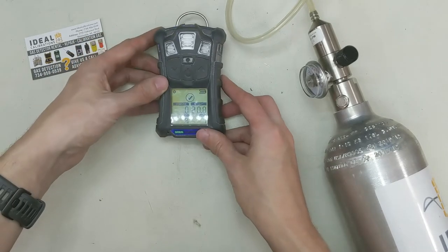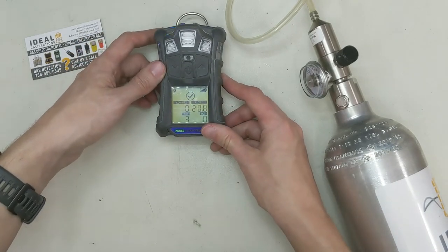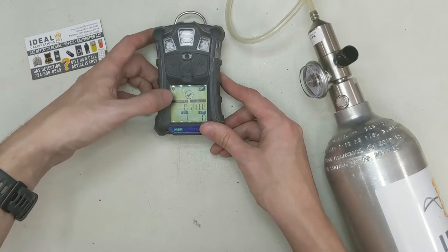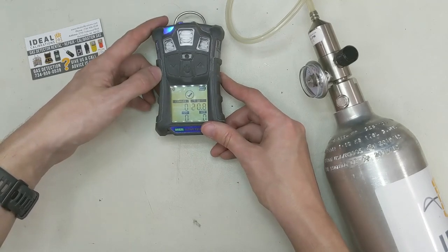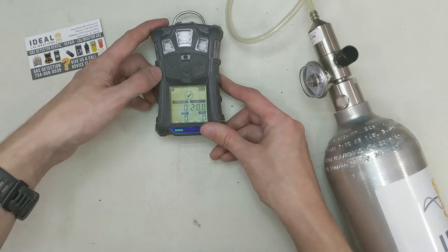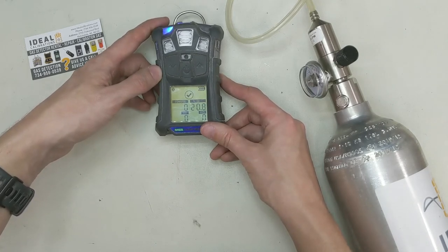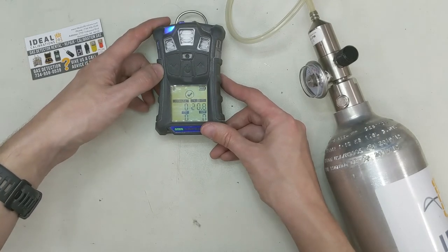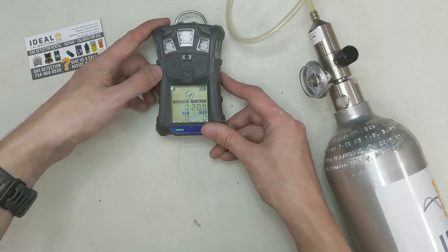We're going to let that go down to zero. And now on these units, like I said, we calibrate these twice in the shop, once for each of those LEL beads. Just in case, that way we know a customer when they get it, they're not getting any surprises. On your end, just you as the end user, I don't think you have to. But if you're a repair shop watching this, I would do it twice. Just something to keep in mind.